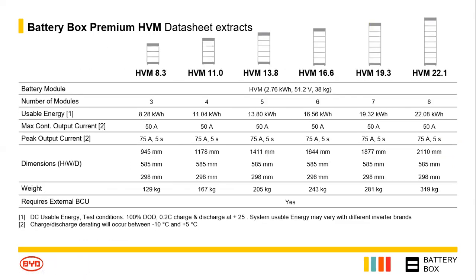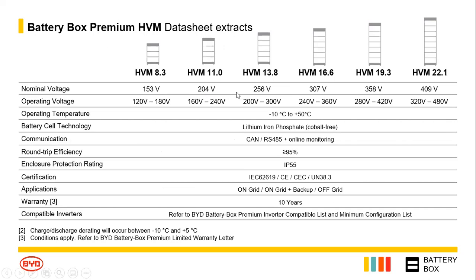The interesting thing about the high voltage batteries is they're a bit different in how they function, or how you install them, relative to low voltage batteries. Here we can see your number of modules - we start at 3, and we go up to 8. As you put on an extra module, the maximum amount of current you can take out stays at 50 amps, however your voltage goes up. This is done so that you can match your nominal voltage depending on usage, which is how it differs from the low voltage installations.